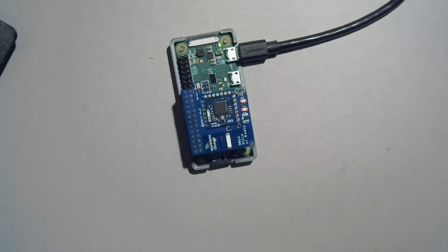Further down, there's a history page, which is more generic information about the pump. It's really just generally speaking what's going on in the pump. If I calibrate my CGM, or if I set the date and time, change the battery, any one of those things that would happen gets written into the history so that you can debug and troubleshoot. So that's the history page. And ultimately, it really just supports those 4 things. And up until now, that's been good. But tonight, I want to add a different one.